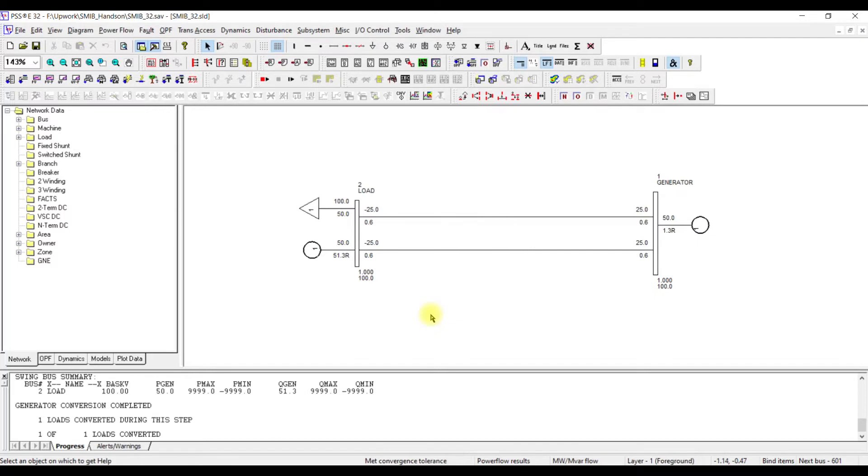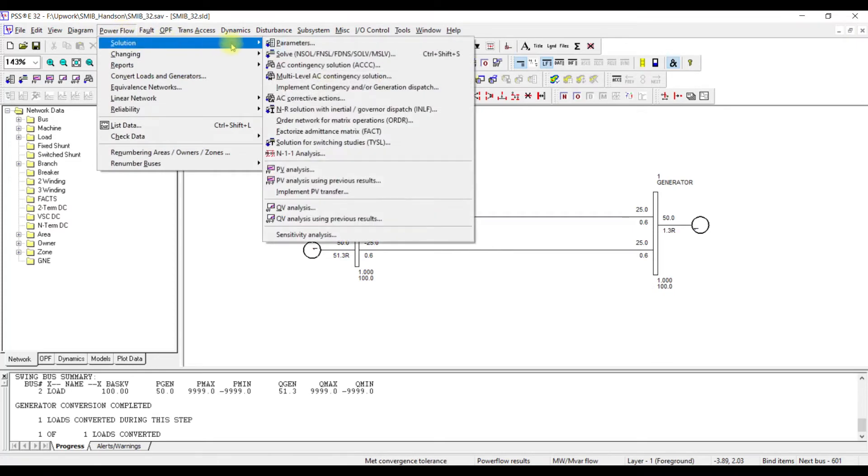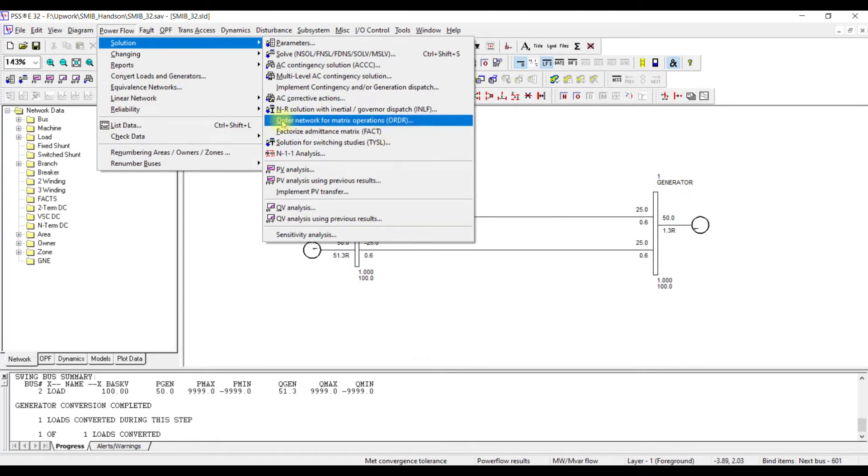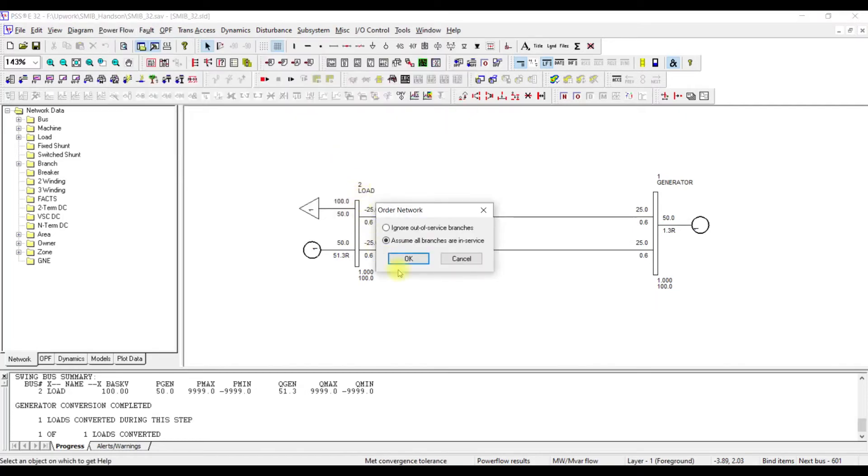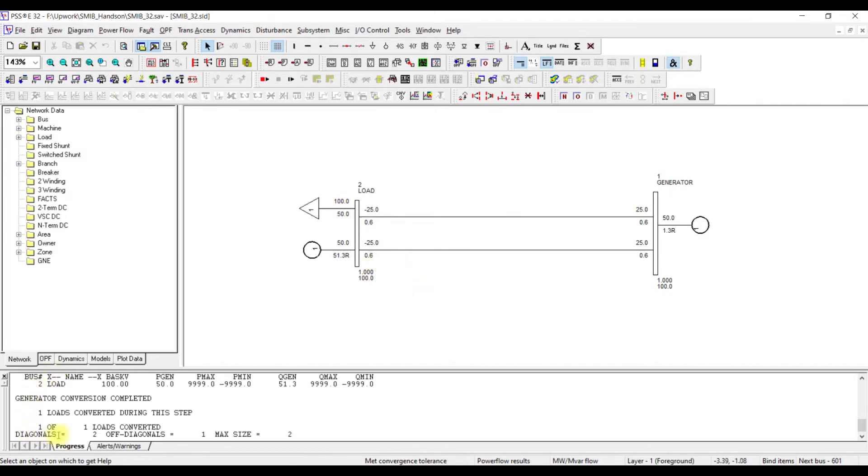But, this system still needs to be further processed. Why we need to process this system further? Because now we have converted into current injection source. Now, we need to convert the algebraic equations out of this. To perform the equations, we are going to use power flow, solution, and we are going to use FACT - factorize admittance matrix. Before factorizing, we have to perform this order network for matrix operation. By this ordering, we are trying to tell PSSE is that please create a matrix for this current, assuming this current injection sources. For this we are going to assume all branches are in service. Now my matrix has been created because this consisted of only two buses. We have a two by two matrix here.